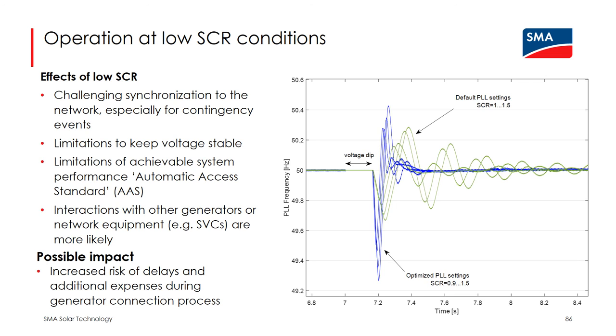one has to consider that the most optimal or most dynamic performance of the generator is typically not achievable. And for the later interconnection studies or wide area studies that are performed, it is quite likely that there will be some kind of interaction with other generators or other network equipment, and this simply needs to be considered in the generator connection process. So for the project developer, it is important to understand that the lower the SCR, the higher the risk of delays or even additional expenses if countermeasures, which may be the installation of additional equipment, need to be taken.